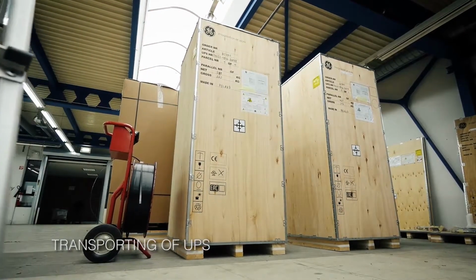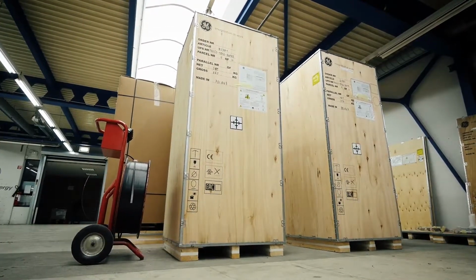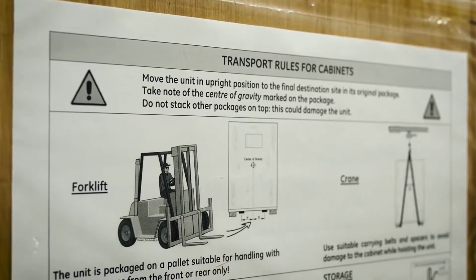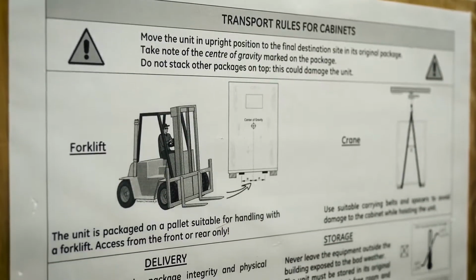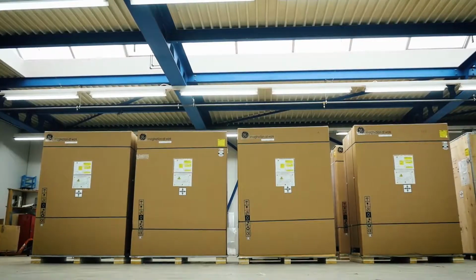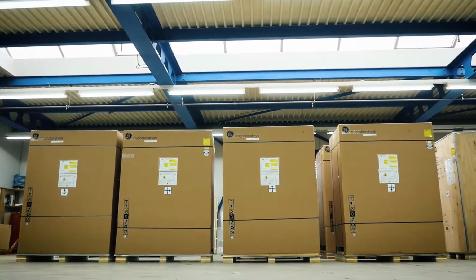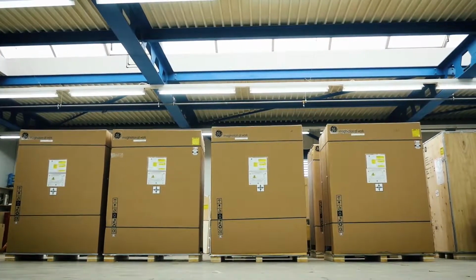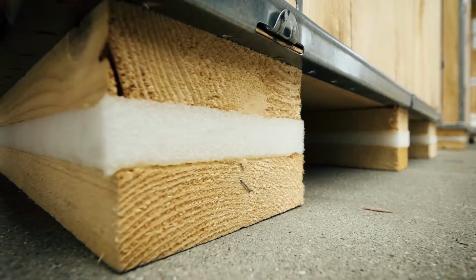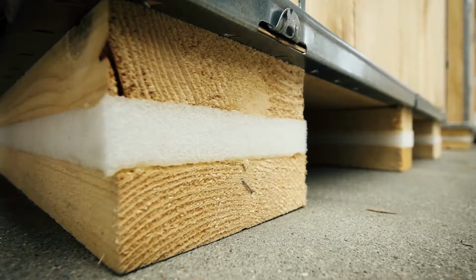A UPS should be handled without batteries and strictly vertically. If you put the unit on its side, heavy modules inside the UPS could fall from their fixings. Therefore, a UPS should be put on pallets that have a layer of polyether foam to counteract vibration.